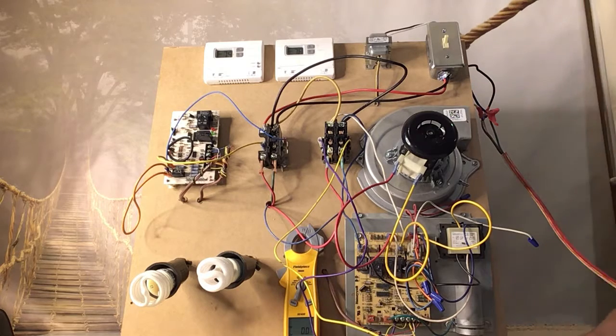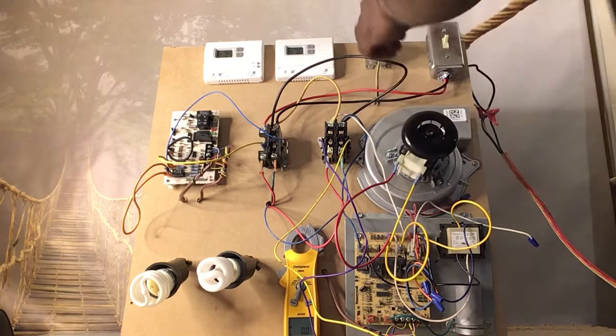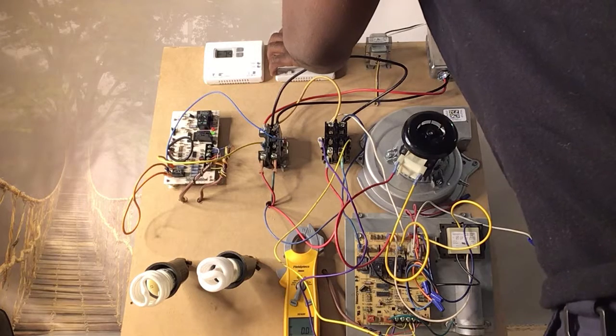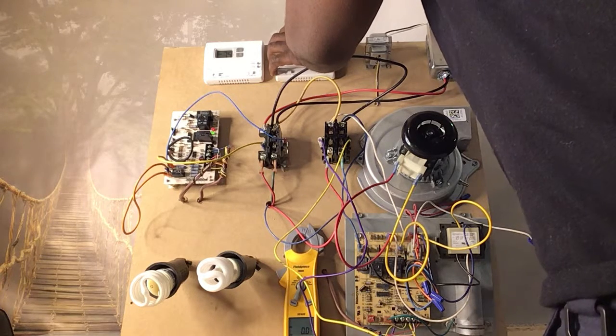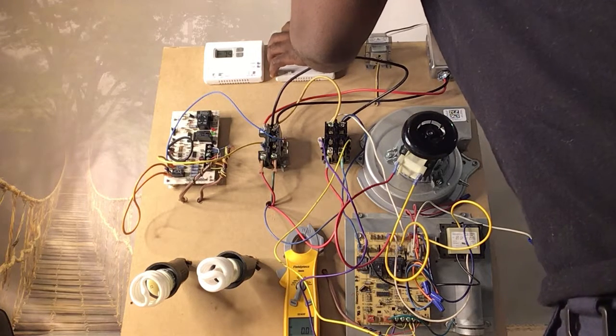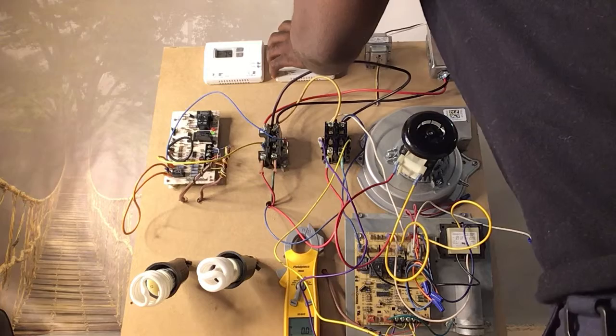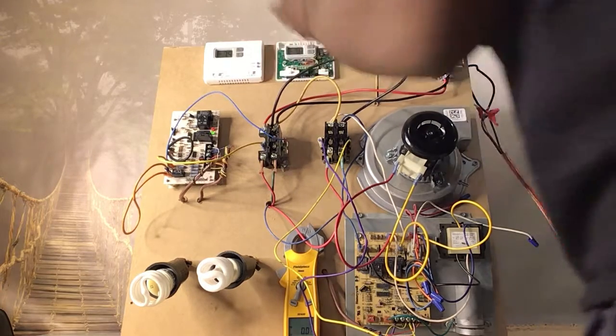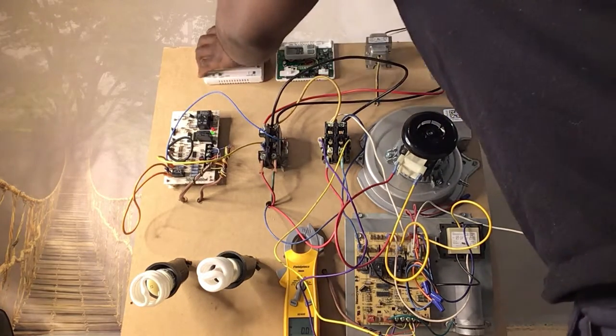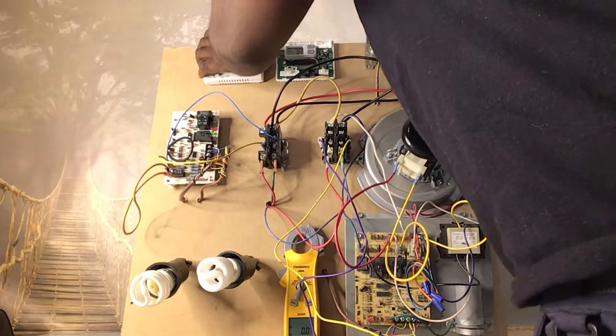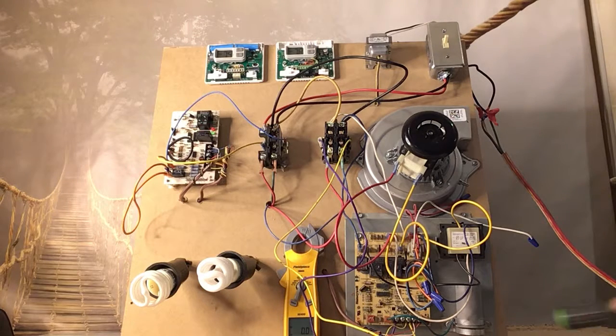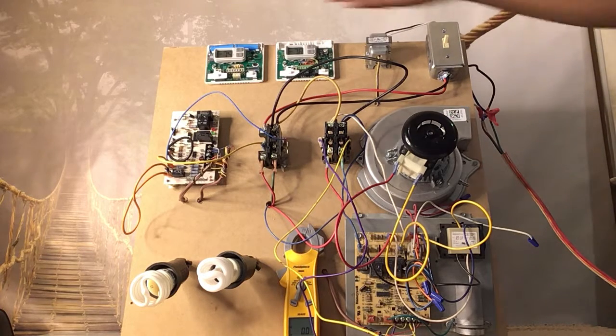Two, you go to your thermostat, and I'm gonna pop this off. And just today we're just gonna be totally checking voltages so that we can see what it's supposed to be doing, what, when, why, and where, and what voltage it should actually have on it, and how to check voltage to see if you actually have a call on your system. All right. So I don't know if y'all can see that or not, but this is the typical wiring setup for a heat pump application and then the straight AC application.